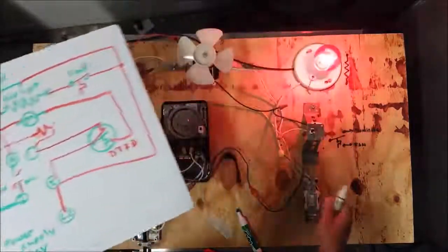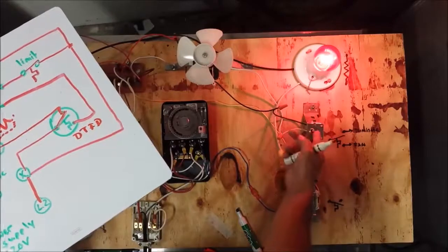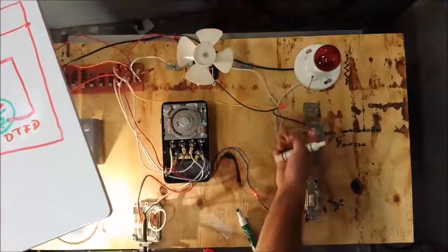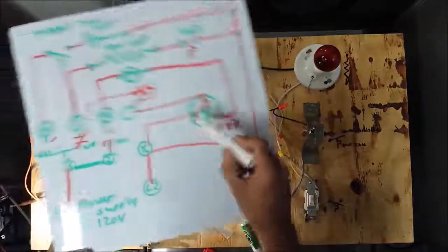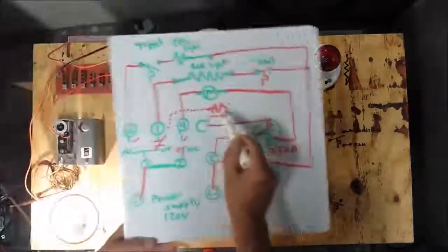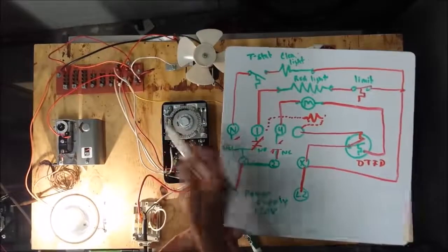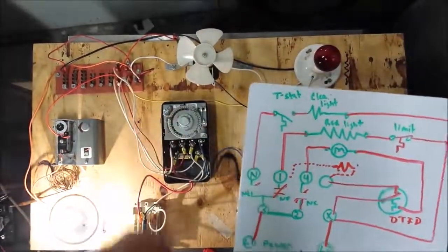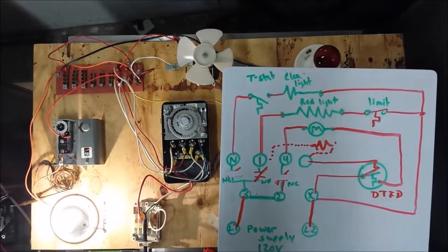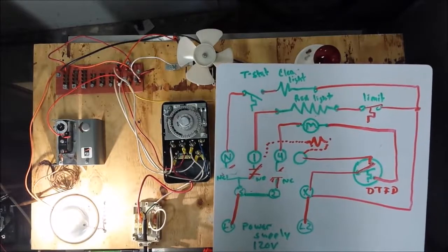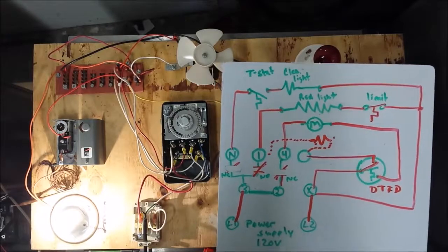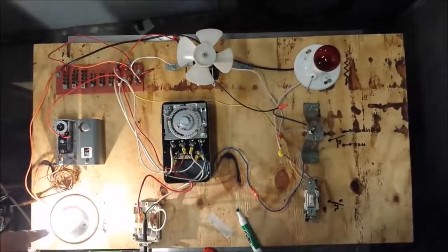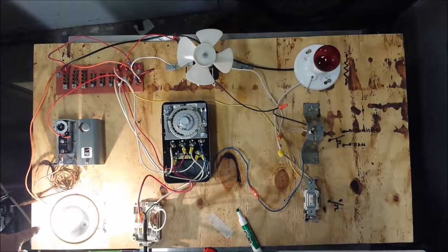So let's check it out. So temperature goes up, temperature's rising, thermostat made the switch, which energized our coil behind the clock, which kicked it out of defrost, even though the clock may show that it's still in defrost. Okay? And now our light bulb back on over here represents our coil to our valve.